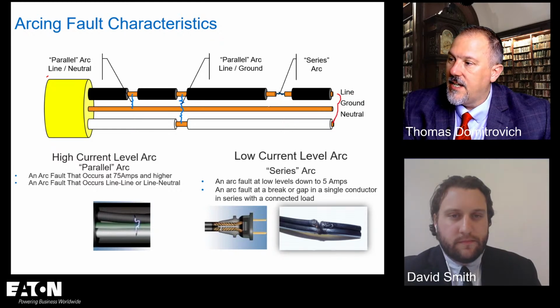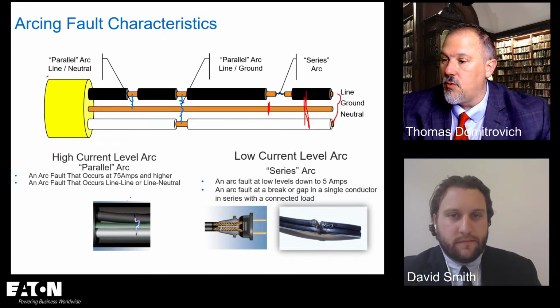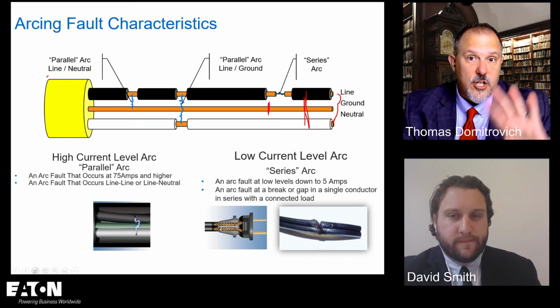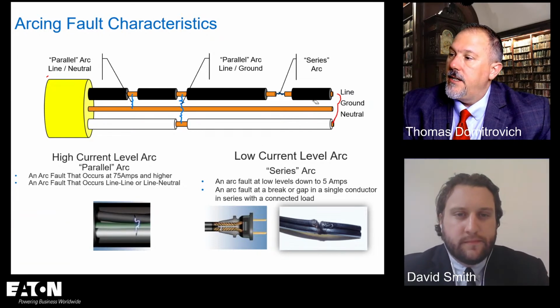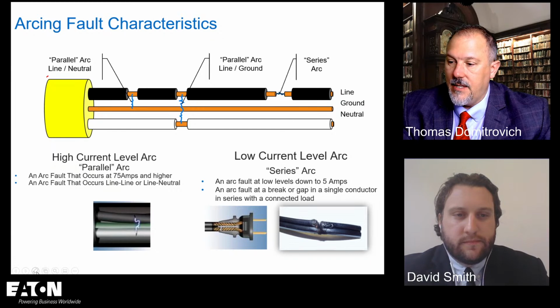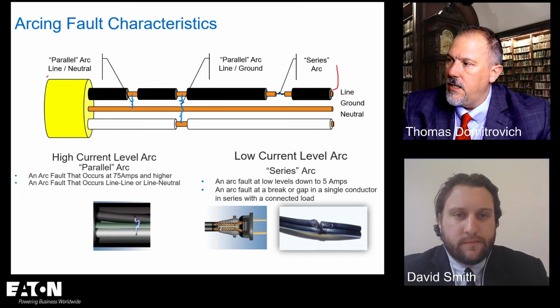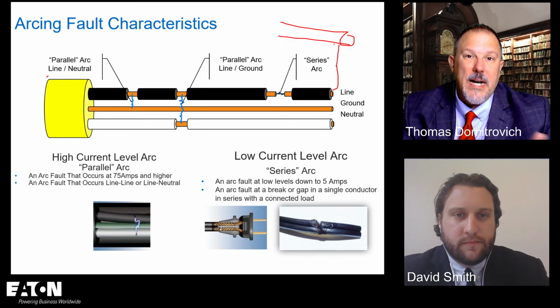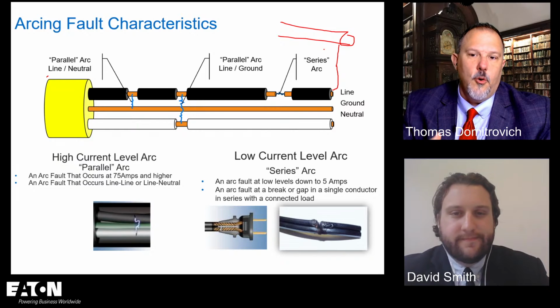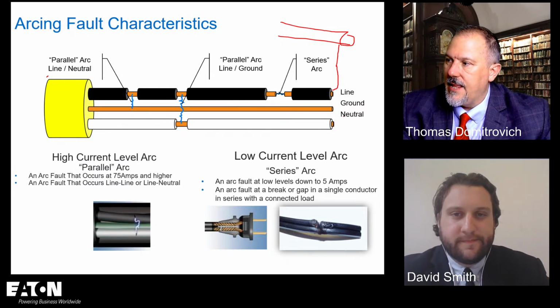For one of the tests, we cut this copper conductor out of the picture and create a fault line to line that doesn't include the equipment grounding conductor, so it's not going to ground. We also do a test from line to, say, a metal pipe. It could be conduit, or just steel pipe, and we make sure that we can detect that arc. I believe we do it on the neutral side too. We have an arc there as well.